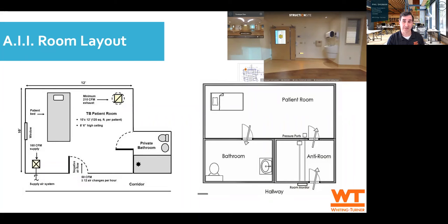Another best practice to be considered is the airflow within the room. We know the room itself has to be negative to the corridor, but you also want the airflow to go from the corridor or the foot of the bed, where the medical practitioners are going to be standing, towards the patient, and have the exhaust ideally over the patient. In this example on the left, it's coming in on the corner, goes across the bed and over towards the diffuser in the far corner.